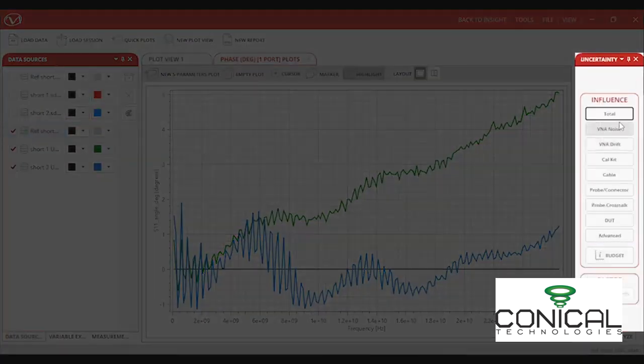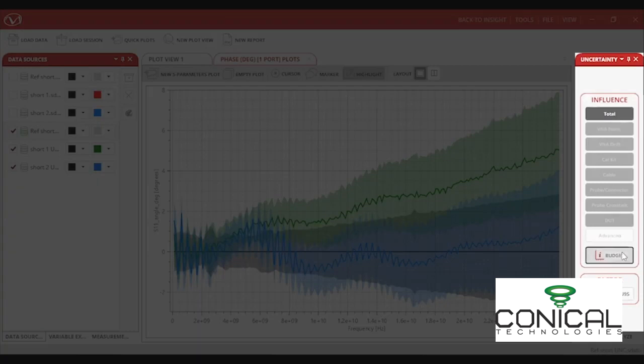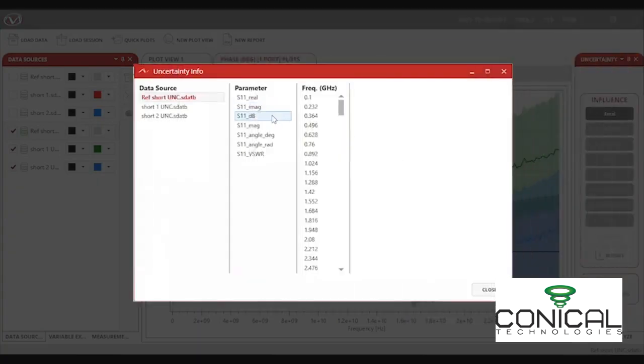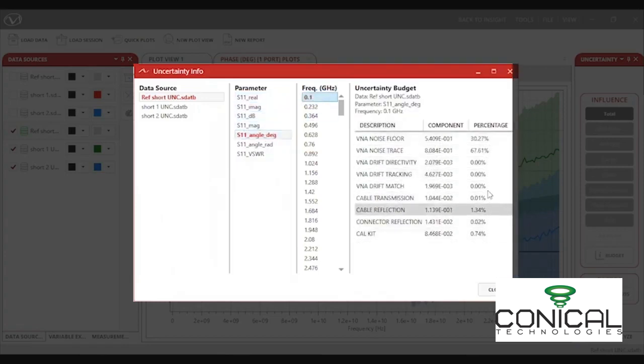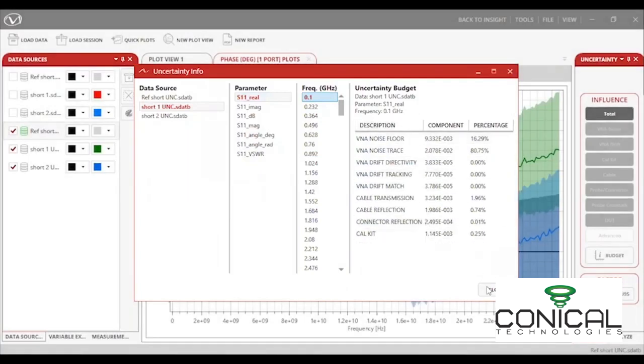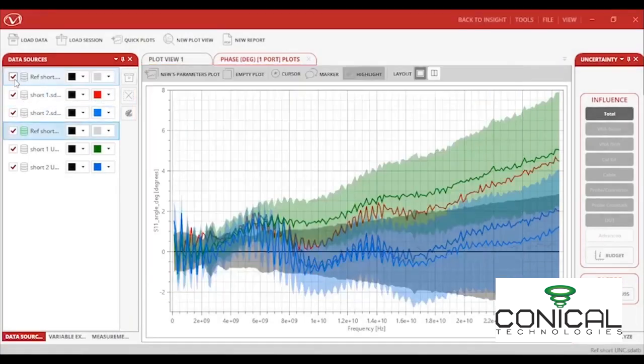I'll next enable the total uncertainties to be displayed. In the budget pop-up window, it displays the individual uncertainty contributions coming from the equipment that was characterized. The uncertainty budget can help pinpoint the source of inaccuracy in your calibration so that you know exactly what to change about your setup to improve your system performance. For example, if the cable is a source of max uncertainty, you now know what to replace rather than having to troubleshoot other components in the system, which can be a huge addition to the capabilities of the 8510.